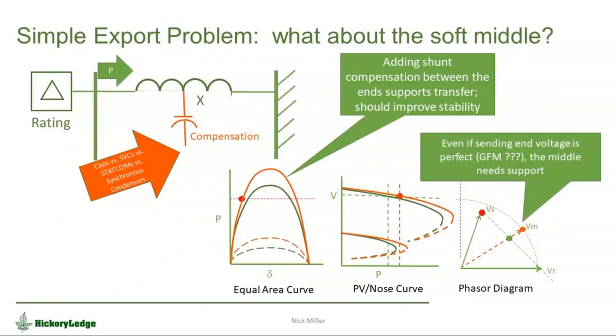So then the next problem here is that these systems are actually long and stringy and we've got to support the voltage in the middle. So now I'm going to concentrate on the orange middle here. So I've got some compensation. Remember, if you look at the phasor diagram on the right, if I support the voltage in the middle, then that tent pole is bigger. It's no longer in the straight line between VR and VS. The nose curve gets better in orange. The power transfer curve gets better in orange, and everything is improved by the presence of some compensation in the middle of the line.